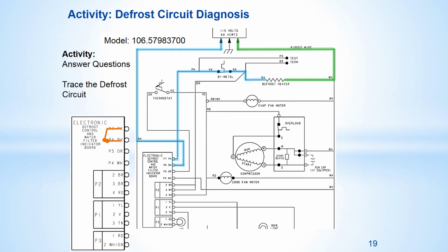Question number 2. How would you know if the defrost heater is functioning without seeing it, hearing it, or feeling it? As stated before, the heater current can be measured anywhere in the heater circuit. Where could all of the electrical circuit checks be made? The ADC board is the logical place since this is the hub of most of the circuits on the refrigerator.